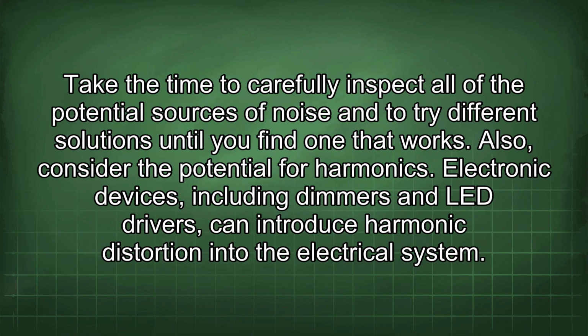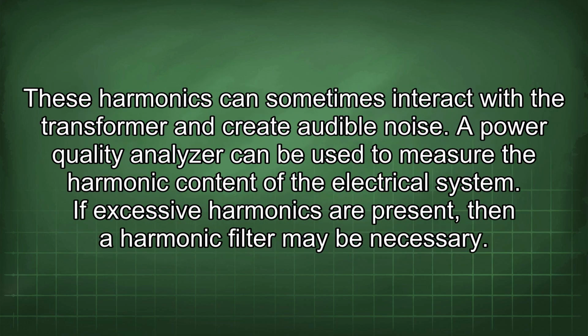Take the time to carefully inspect all of the potential sources of noise and to try different solutions until you find one that works. Also, consider the potential for harmonics. Electronic devices, including dimmers and LED drivers, can introduce harmonic distortion into the electrical system. These harmonics can sometimes interact with the transformer and create audible noise. A power quality analyzer can be used to measure the harmonic content of the electrical system. If excessive harmonics are present, then a harmonic filter may be necessary.